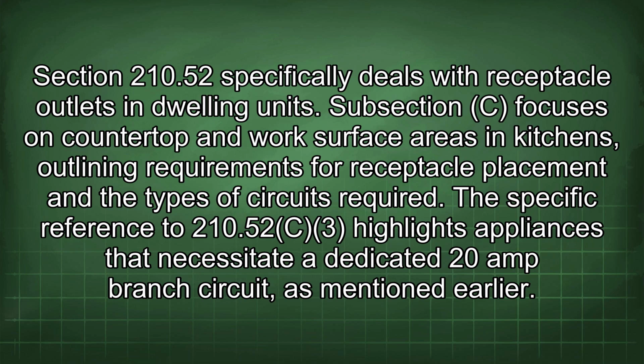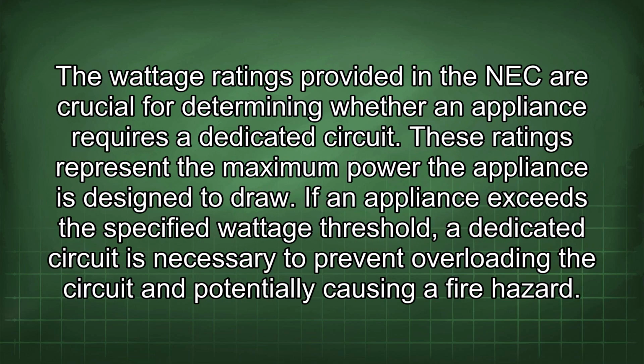The specific reference to 210.52(C)(3) highlights appliances that necessitate a dedicated 20-amp branch circuit, as mentioned earlier. The wattage ratings provided in the NEC are crucial for determining whether an appliance requires a dedicated circuit. These ratings represent the maximum power the appliance is designed to draw. If an appliance exceeds the specified wattage threshold, a dedicated circuit is necessary to prevent overloading the circuit and potentially causing a fire hazard.